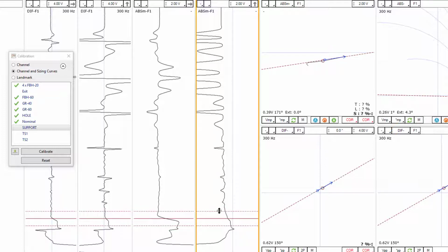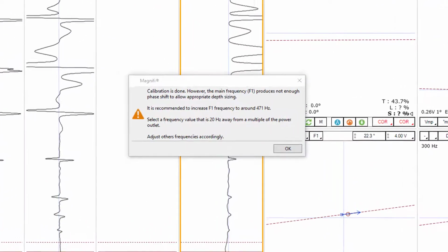And what you look for is that this big dot line here should be in line with the straight portion of the support. It's not important the orientation of the vector, as long as this dot line is parallel to the straight portion of the support, the measurement is okay. So you make sure it's selected, you measure and calibrate.